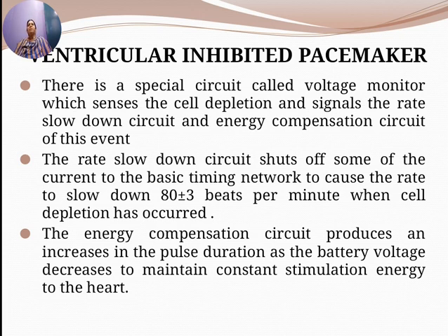The energy compensation circuit produces an increase in the pulse duration as the battery voltage decreases, to maintain constant stimulation energy to the heart.